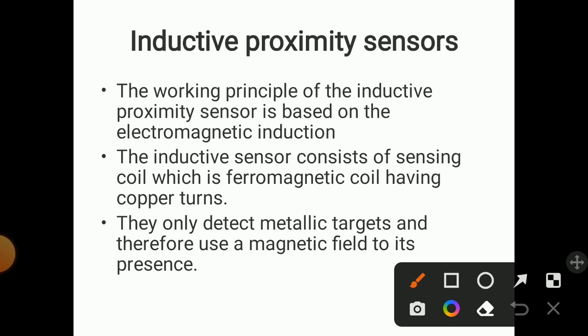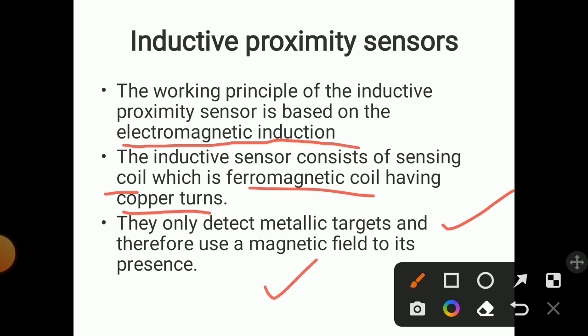The working principle of inductive sensors is based on electromagnetic induction. When an electric signal is given, the coil generates a magnetic field. The inductive sensor consists of a sensing coil, which is a ferromagnetic coil with copper turns. These sensors can detect metallic targets only — they use a magnetic field to detect their presence.